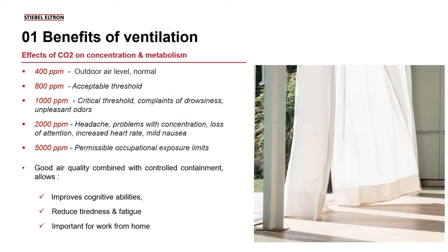In places of work, or even in our own homes, we can build up concentrated levels of CO2, which can have negative effects on our health. Acceptable levels of CO2 within the air we breathe are up to 800 ppm. Once we reach a critical threshold of 1000 ppm, we start to notice negative symptoms, such as drowsiness and unpleasant odours. If we double that to 2000 ppm, we may start to experience headache, problems with concentration and lack of attention, increased heart rate, and even mild nausea. 5000 ppm is the maximum permissible occupational exposure limit.